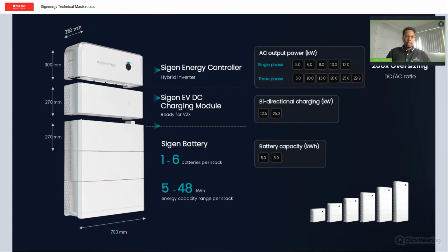The batteries come in 2 sizes, either 5 kilowatt hour or 8 kilowatt hour, and you can mix and match. If you have parallel multiple stacks, you don't have to have the same inverter on top, the same number of battery modules, or the same type of battery modules. The only thing I'd say is that because we can have multiple combinations, CEC made us list it as a pre-integrated BESS system, so just double check the combination you're after is CEC approved. We've got more combinations in the pipeline to be approved as well.